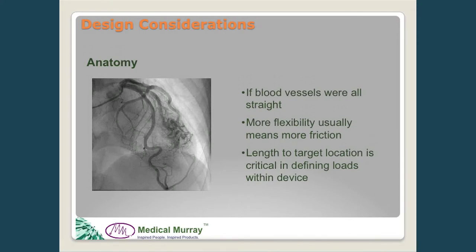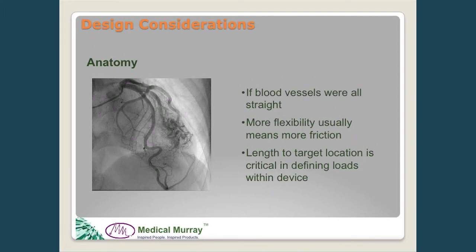The second consideration is anatomy. If all blood vessels were straight, life would be easy, but as we can see in the picture, they're not. We have to introduce flexibility into the device, and with flexibility come tackier plastics, tackier surfaces, and more friction. We have to take tighter turns into smaller locations, deal with reduced wall thicknesses, lumens that want to go oval or kink, and more surface contact between components. We also have to consider the length of the target location, as devices become longer the magnitude of these loads increases.